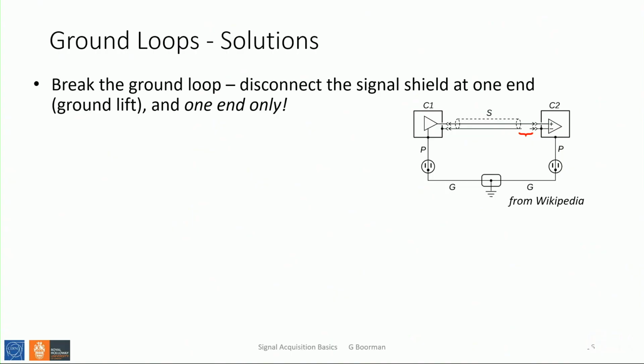So you end up with the signal coming out of your signal source, you measure it, and there's physically no loop, so there's no induced current on it. If that break is really, really physically long, so you end up with effectively a bit of cable with no shielding, you can also pick up other signals - but assume the break is quite small and it will work quite nicely.